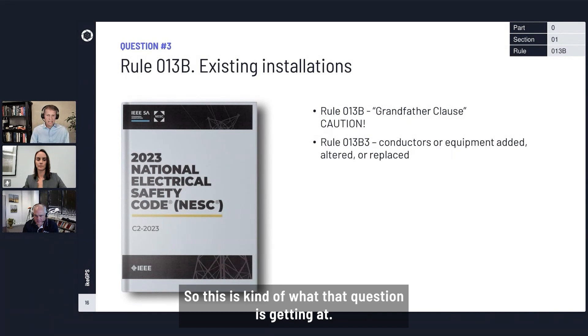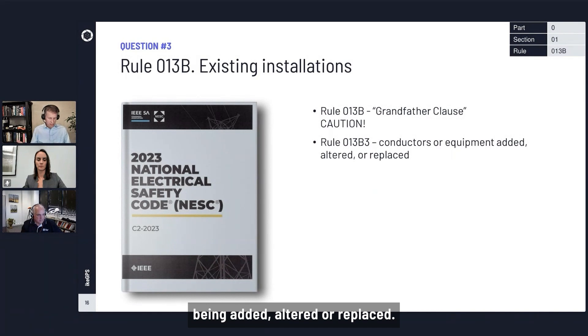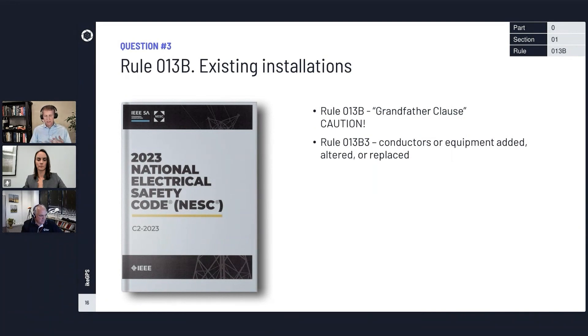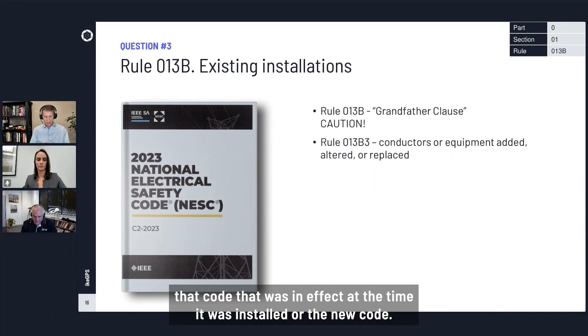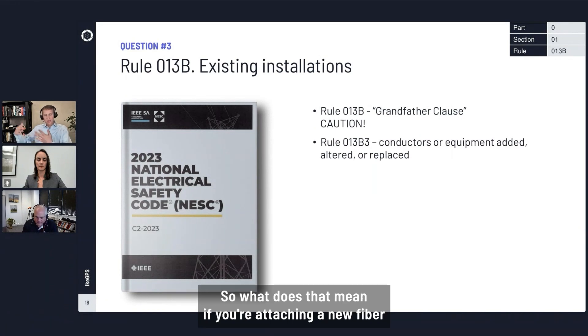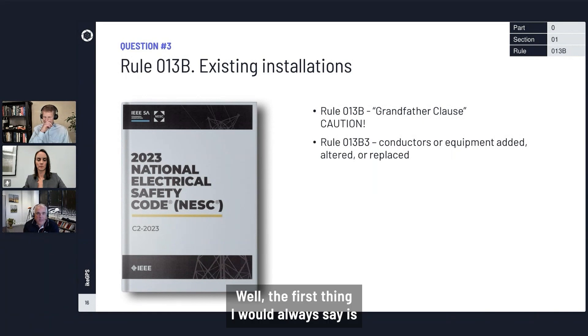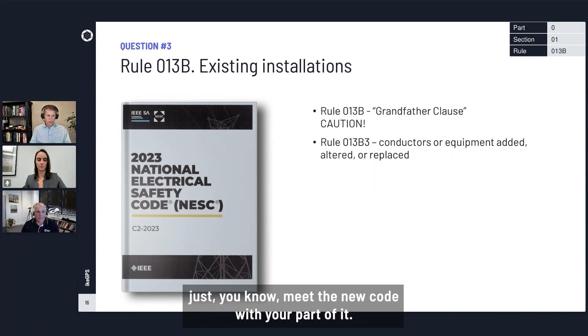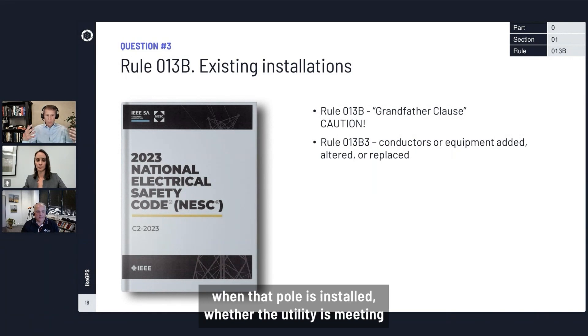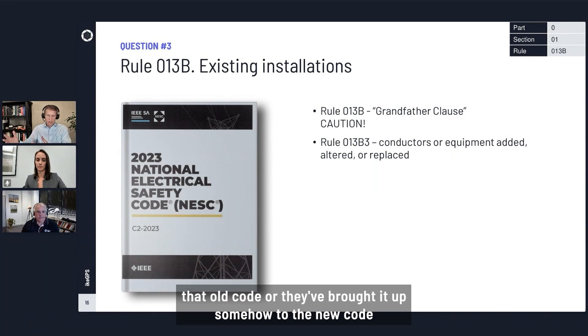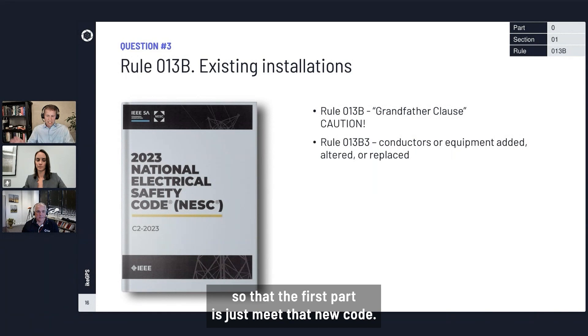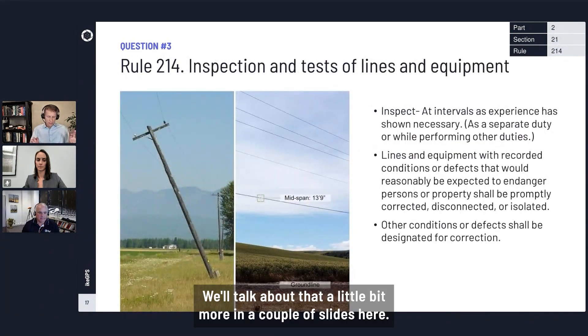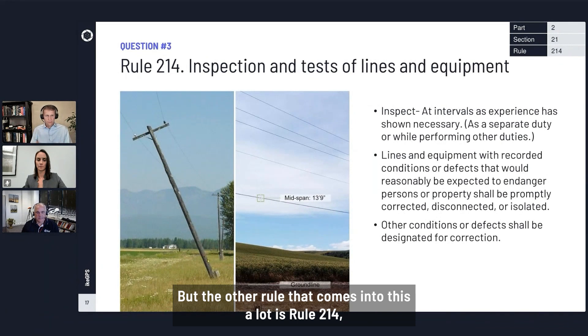Rule 013 b3 talks about conductors or equipment being added, altered, or replaced — and when that work is done, the resulting structure has to meet either the code that was in effect at the time it was installed or the new code. So what does that mean if you're attaching a new fiber optic cable? The first thing I would always say is just meet the new code with your part of it. You don't usually know, as an attaching entity, whether the utility is meeting that old code or has brought it up to the new code.